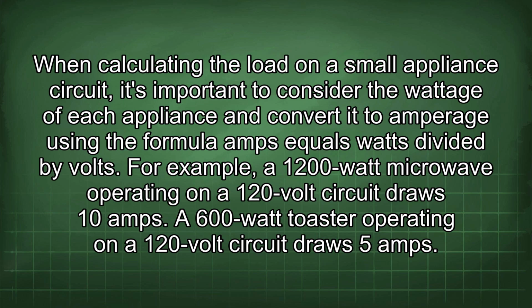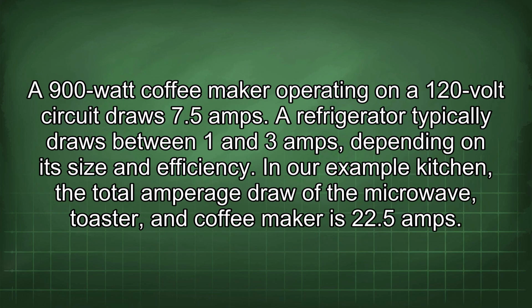When calculating the load on a small appliance circuit, it's important to consider the wattage of each appliance and convert it to amperage using the formula amps equals watts divided by volts. For example, a 1200 watt microwave operating on a 120 volt circuit draws 10 amps. A 600 watt toaster operating on a 120 volt circuit draws 5 amps. A 900 watt coffee maker operating on a 120 volt circuit draws 7.5 amps. A refrigerator typically draws between 1 and 3 amps depending on its size and efficiency. In our example kitchen, the total amperage draw of the microwave, toaster, and coffee maker is 22.5 amps.